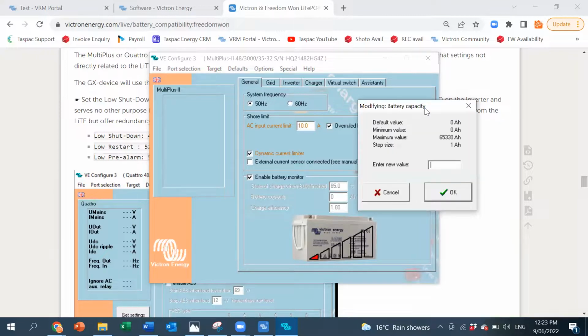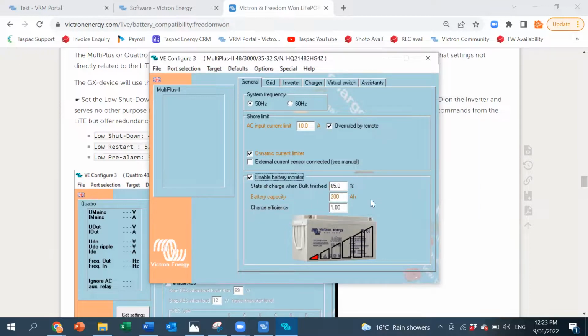Usually a lithium, you just convert kilowatt hours divided by 50 volts equals amp hours. So a 15 kilowatt hour battery will be 300 amp hours. So we could put, say, 200 amp hours in there. This is actually not going to be used when the lithium battery is connected. But if someone trips over the data cable or there's a problem with the comms, it will then revert back to this inverter to manage the battery itself. So normally I would put in a lower amp hour rating than what the battery actually is. Or if I know what the battery is, put it bang on what battery size is.